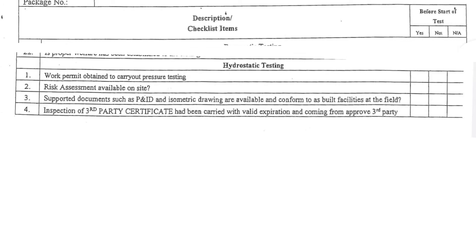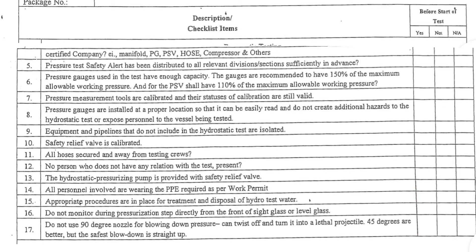Hydrostatic testing. 1. Work permit obtained to carry out pressure testing. 2. Risk assessment available on site. 3. Supported documents such as P&ID and isometric drawing are available and conform to as-built facilities at the field. 4. Inspection of third-party certificate has been carried out with valid expiration and coming from an approved third-party certified company — for example, manifold, PG, PSV, hose, compressor, and others.